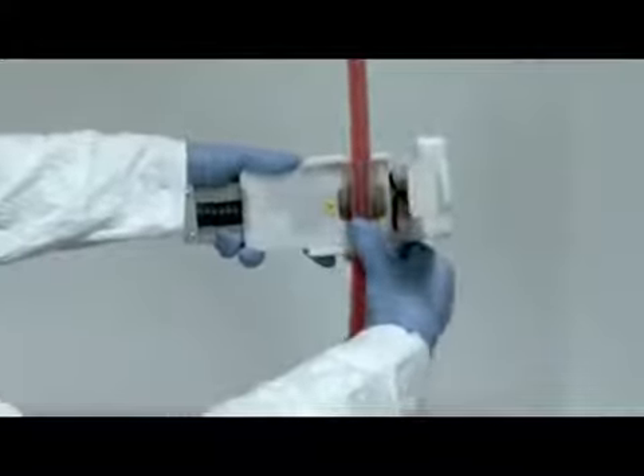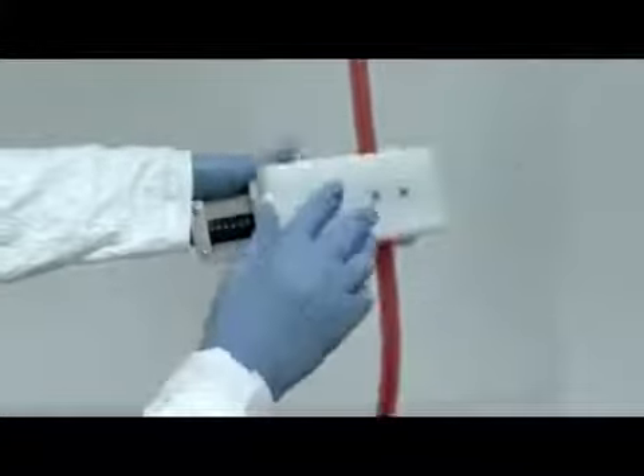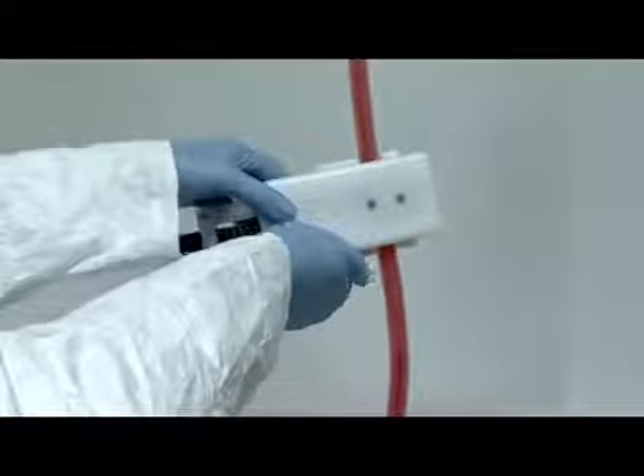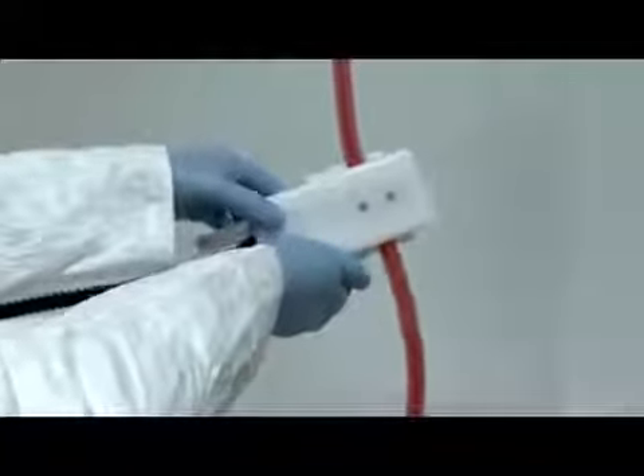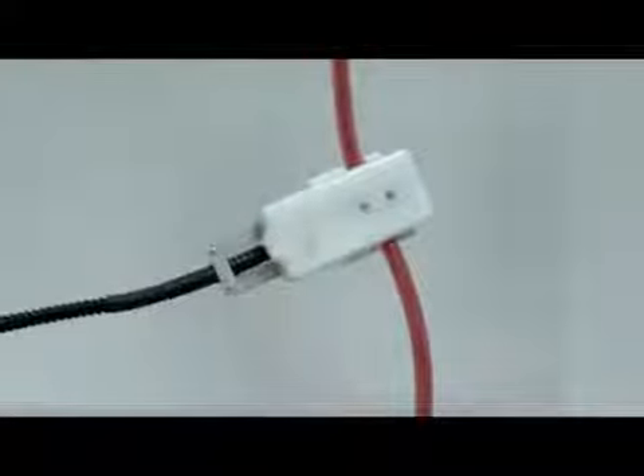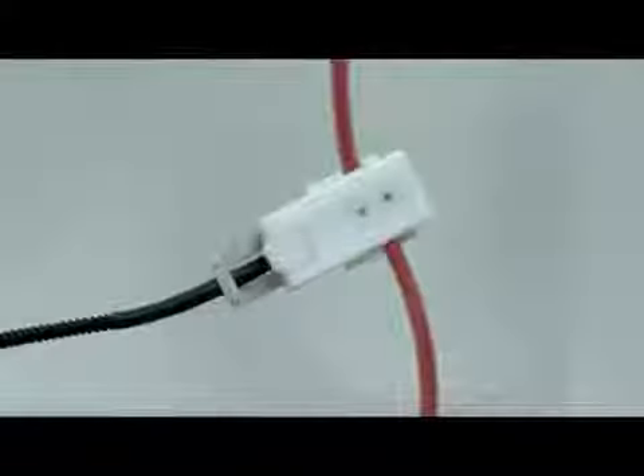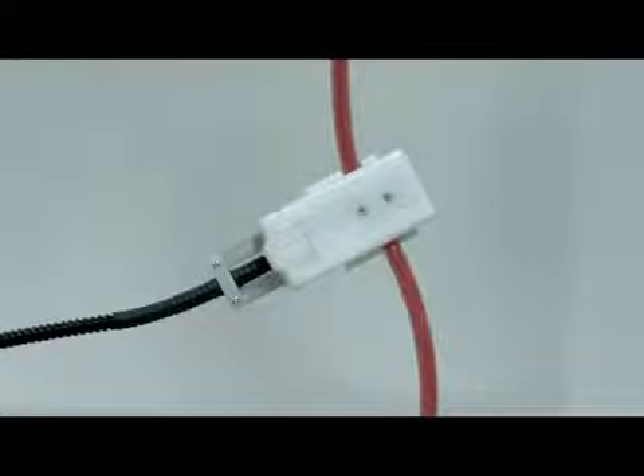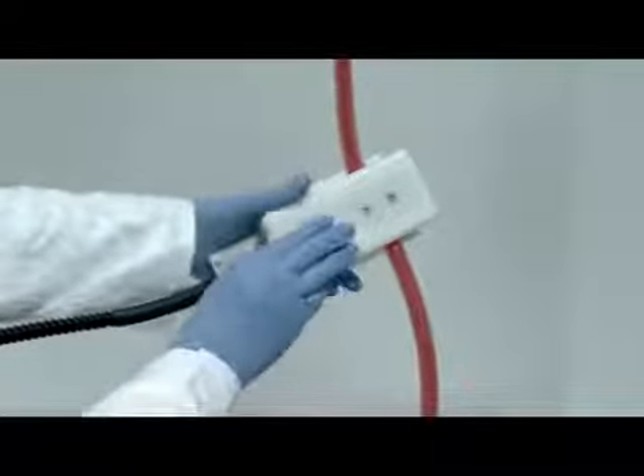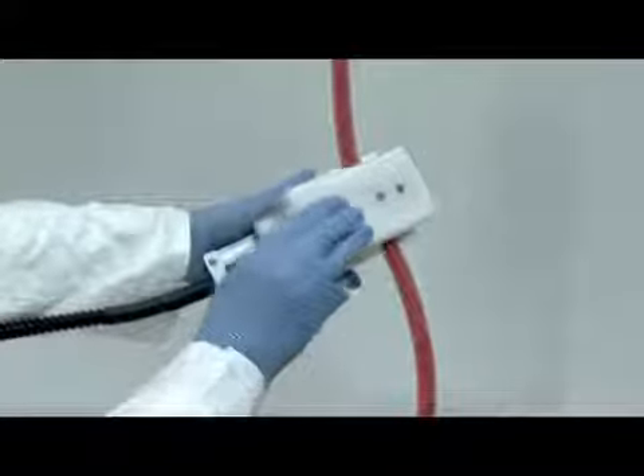This extremely portable sealing head design tethers the head to the power unit, allowing the user to take the sealer to the tubing wherever it is in the manufacturing suite. Pictured is a validated seal being applied to a sterile fluid-filled tubing pathway, performing a seal without breaking sterility.